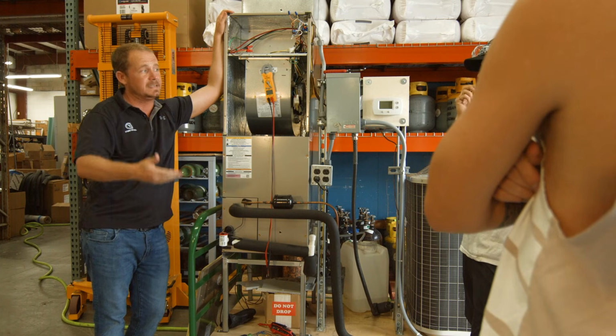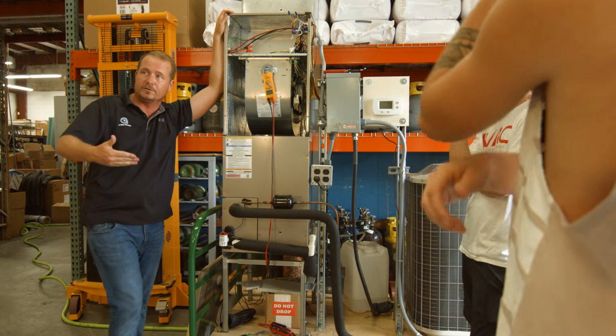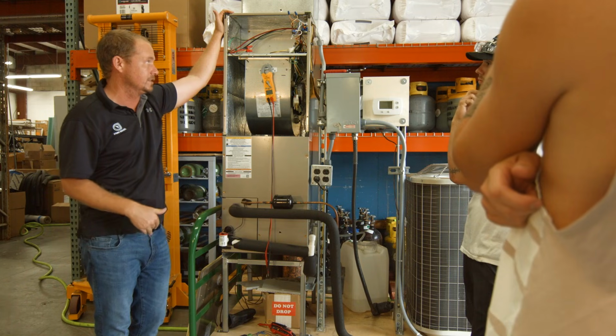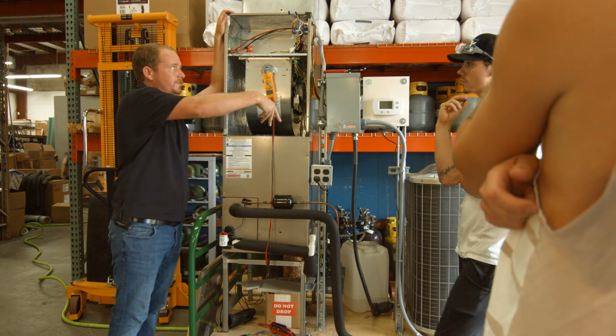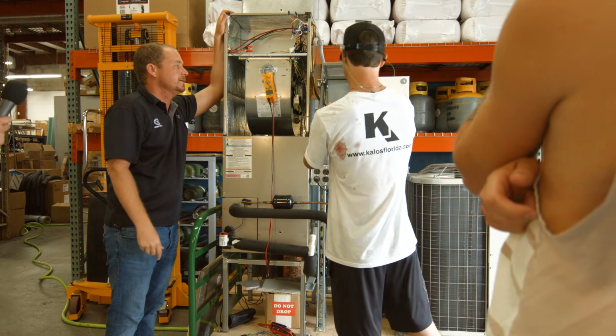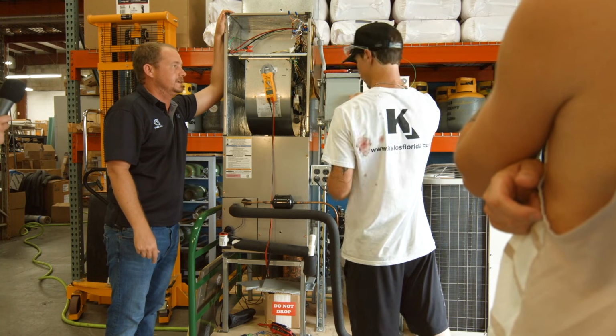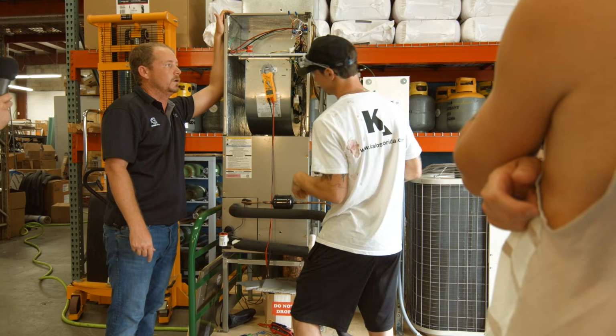So that's something you will see in some cases with short circuits where it won't trip the fuse because it never allows it to stay energized long enough. All right, so now let's do it the proper way. Shut off the breakers, let's disconnect everything, and I'm going to show you the way that I would typically confirm it in one pass, a newer technique.